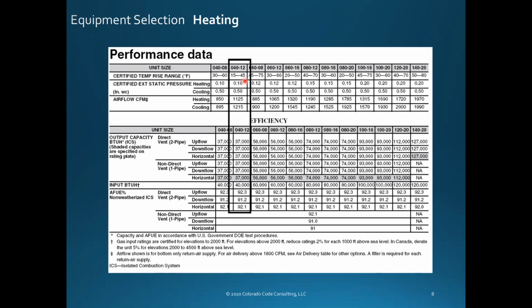So as a designer, I would have increased the airspeed. I'd have gone up one more speed to cool that down a little bit, because we want to be right in the middle. This is where we want to be for temperature rise. Let's talk about this certified external static pressure piece. Do not get bent out of shape with this, okay?